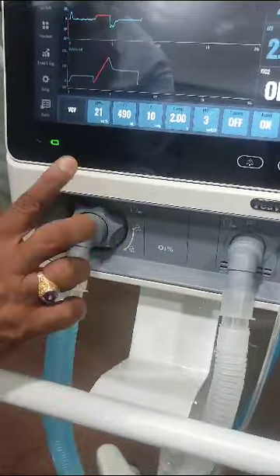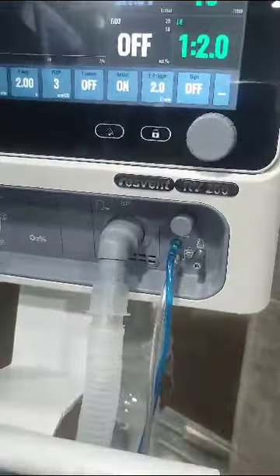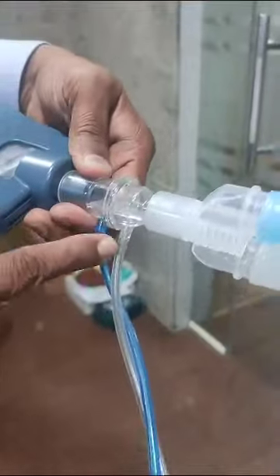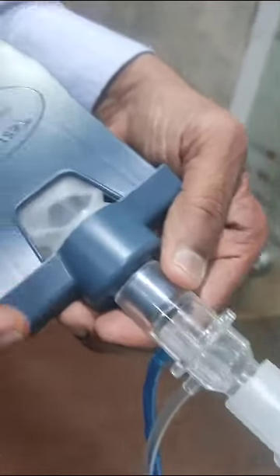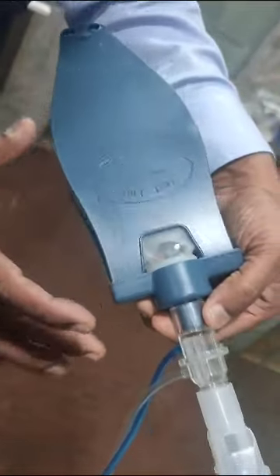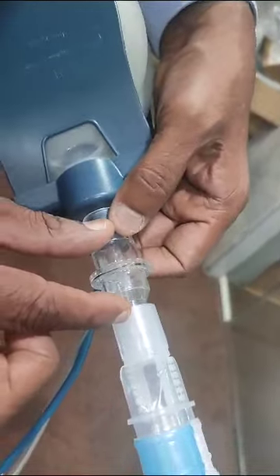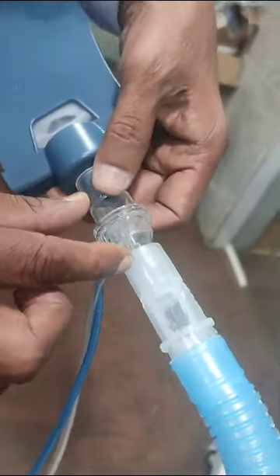Now ventilation has started, and when you are connecting, this is your inspiration going to the patient. This is exhalation going to the expiratory valve, and this is your flow sensor connection. Here is the flow sensor, connected to the test lung. This is the patient. The flow sensor is a proximal flow sensor, which has good accuracy.